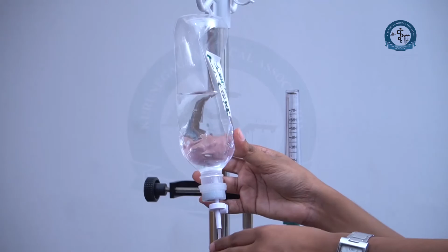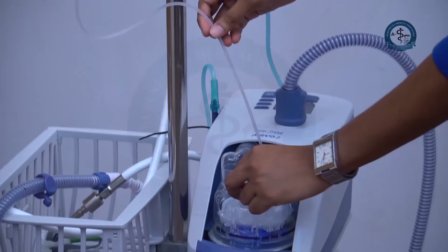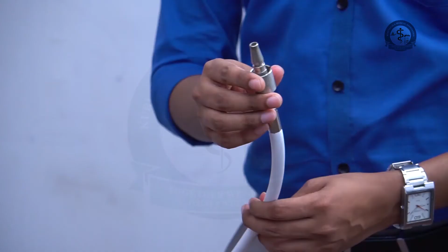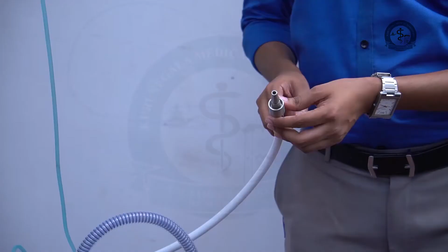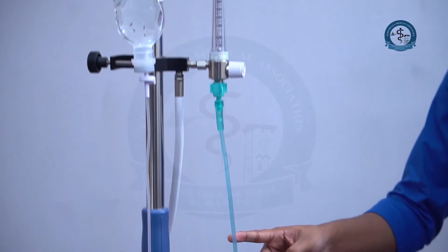A sterile water bag should be connected to the humidifier before starting high flow ventilation. This humidifier can control the water level by using the floater inside the humidifier. The oxygen source, a cylinder or wall oxygen, is to be connected to the main unit. The blue tube which connects the patient to the system should be connected to the main unit. High flow oxygen delivery needs a nasal cannula. Generally it comes in 3 sizes: small, medium and large. The appropriate nasal cannula should be selected according to the patient. The nasal cannula is placed into the patient as follows.